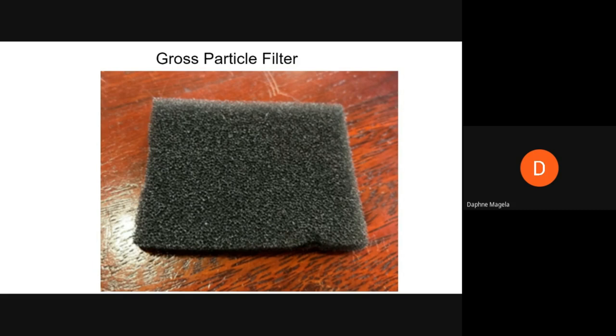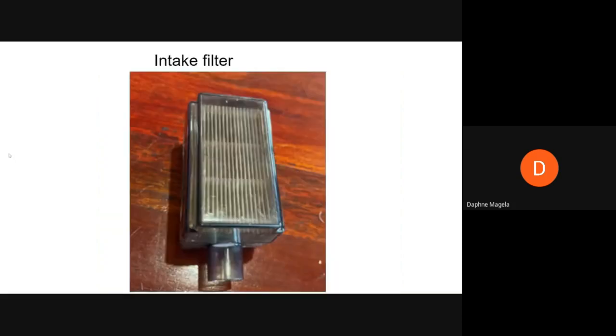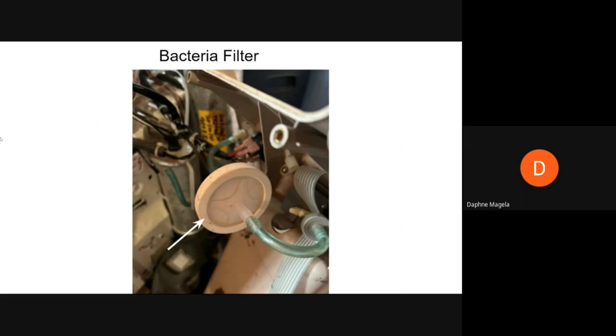All particles not caught by the cabinet filter are trapped by the intake filter. How frequently the intake filter needs maintenance depends on usage and environment — more often in dusty environments. Since most intake filters are sealed, they are usually replaced rather than cleaned. The bacterial filter protects patients from viruses and bacteria. It is rarely damaged; the most frequent cause of damage is water contamination when water from the humidifier bottle travels back into the concentrator. For example, the DeVilbiss 515 service manual specifies the bacterial filter must be changed every two years or 17,520 hours.